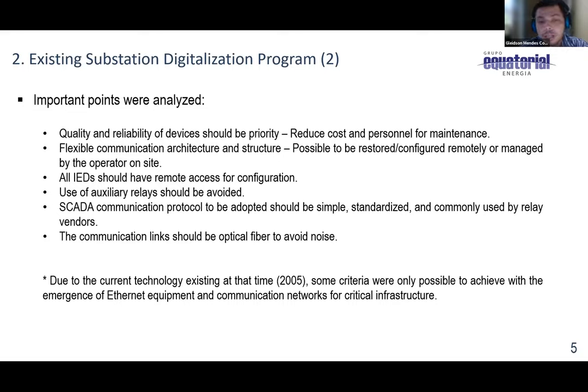Use of auxiliary relays should be avoided because the relay should do all the work by itself. And the SCADA communication protocol for these devices should be simple, standardized, and commonly used by relay vendors. So it would reduce the maintenance cost and reduce the complexity of maintaining the SCADA. The communication links should be optical fiber to avoid noise. Due to the technologies in 2005, some of these criteria couldn't be fulfilled. But with the emergence of Ethernet communications, we could fulfill some of these points, like the flexible communication, for example.